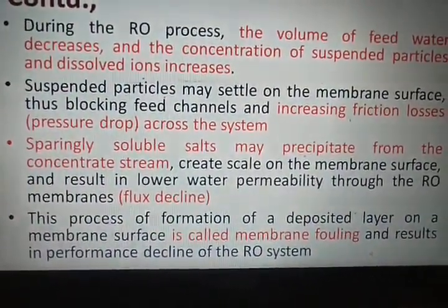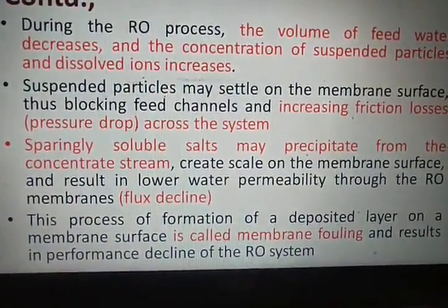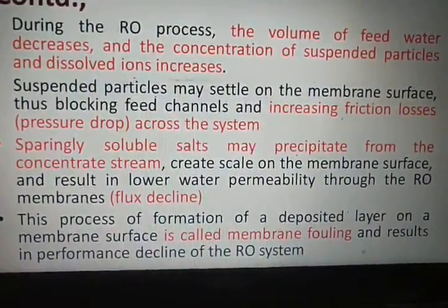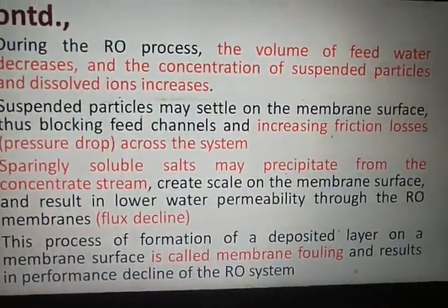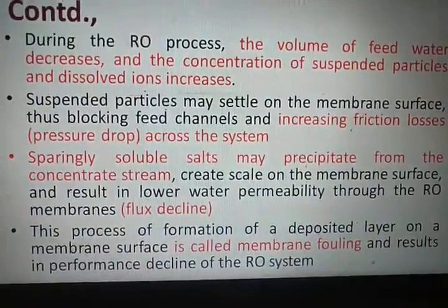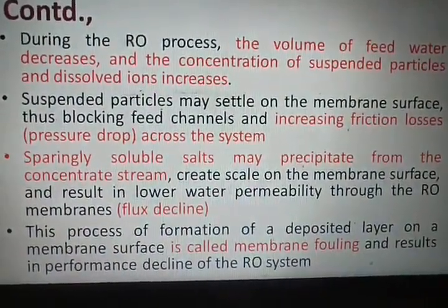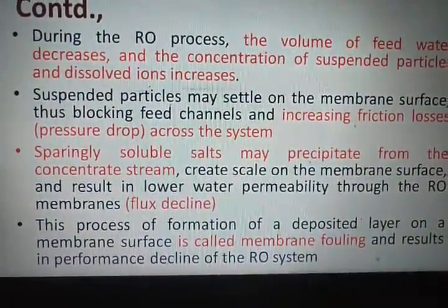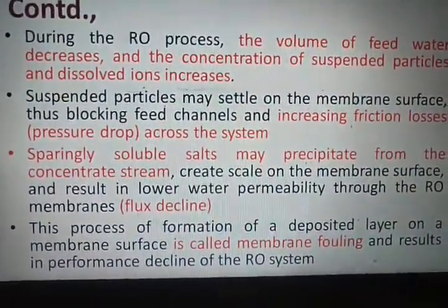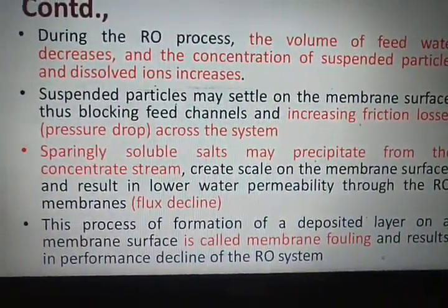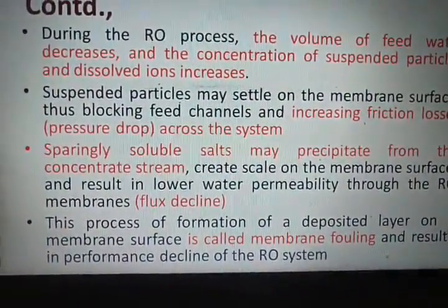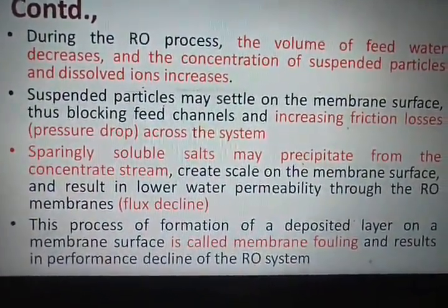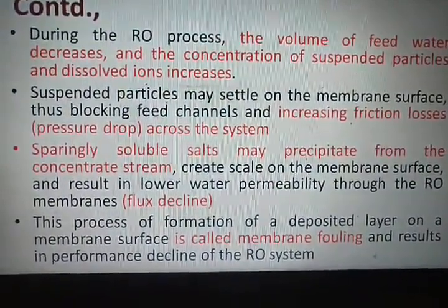These suspended particles may settle on the surface of the membrane, thus blocking feed channels and increasing frictional losses, and it will lead to a pressure drop across the system. And the sparingly soluble salts may precipitate from the concentrate stream and form scales on the membrane surface. Thereby, it will lower the permeability of the membrane, and the flux starts to decline. This process of formation of a deposited layer on the membrane surface is called membrane fouling.